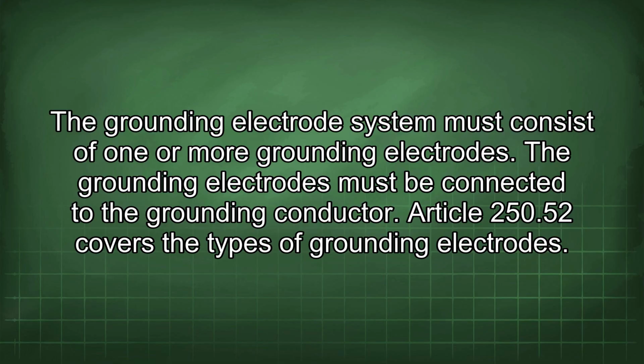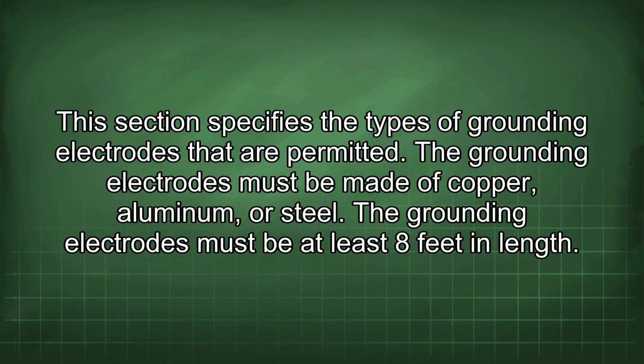Article 250.52 covers the types of grounding electrodes. This section specifies the types of grounding electrodes that are permitted. The grounding electrodes must be made of copper, aluminum, or steel. The grounding electrodes must be at least 8 feet in length.